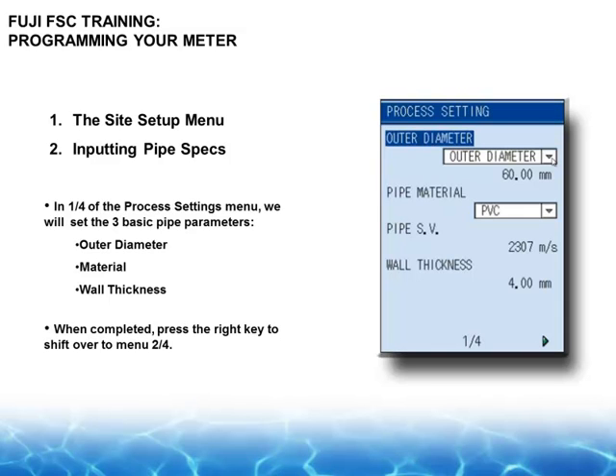Then there's a drop-down menu after that to select your pipe material. It's got a gazillion different flavors of pipe material. If you have something exotic, then go to other, and we have other charts to give you some exotic information. Pipe wall thickness, again, 95% of the time, you're going to have Schedule 40 piping. Most of the time, if you're going to use copper, it's type L piping. If you're going to use ductile iron pipe, it's class 52. These are the high majority of applications that you can put in there. Again, use your ANSI pipe wall chart for that data.